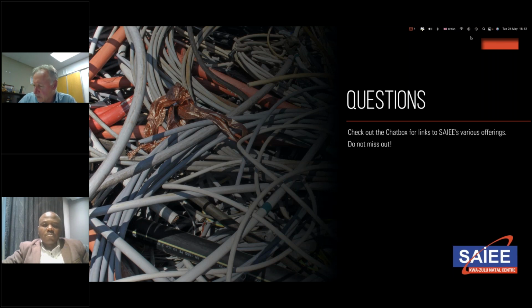So then Michaela, I think it's Michaela, asked a question about automatic severance of a cable once it's pulled by 20 to 50 meters. If I understand the question correctly, it is whether one can build a fail mechanism into the cable that allows only a certain amount of pulling tension, and then the cable breaks. I think one has to balance the need for a robust cable for pulling into installations, and the methods used for installing cables, which put tension on the cable, against this potential requirement to have a cable break when there's too much force on it.